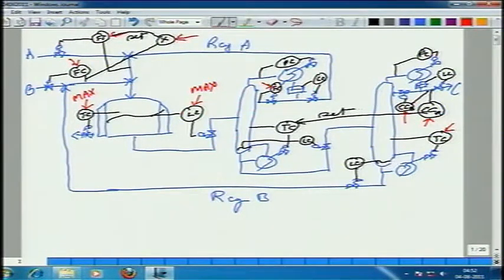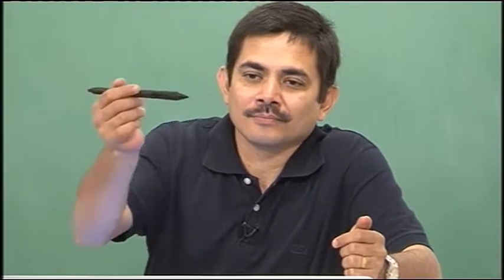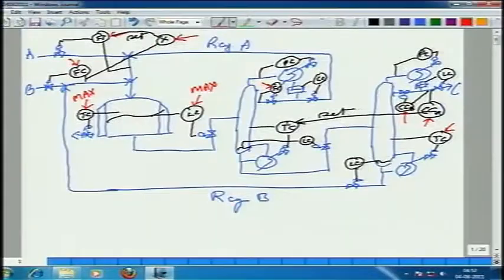Now, the operator is setting this ratio set point and the total B set point. Still 8 things, he is still setting 8 things, but this is a more reasonable way of doing things. It automatically gets you close. What does this flow controller do? The set point of the total B flow controller will be used to increase or decrease throughput.